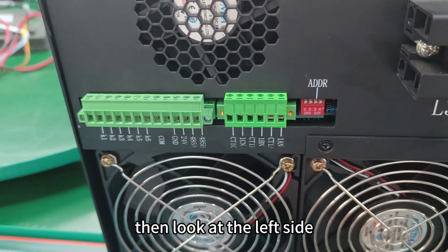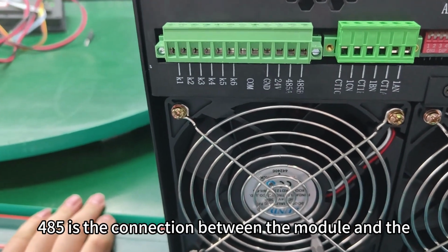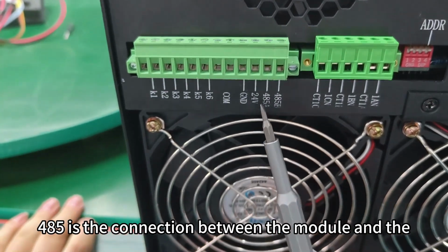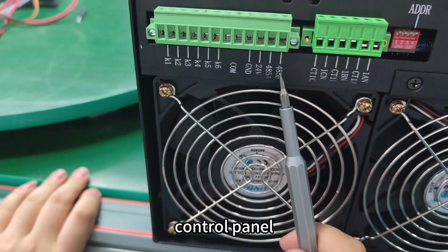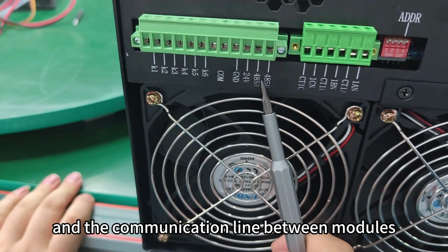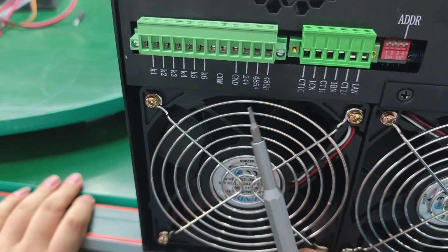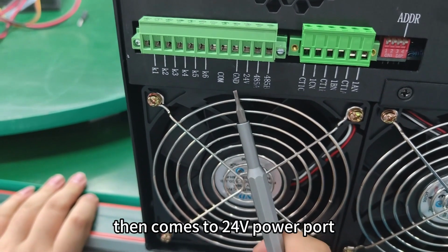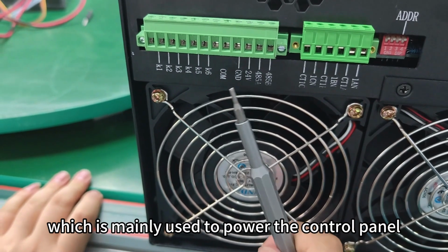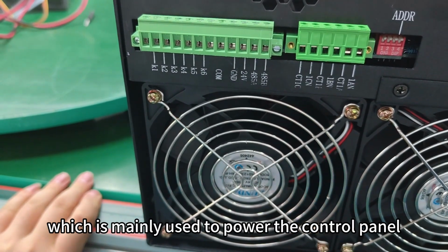Then look at the left side. 485 is the communication between the module and the control panel, and the communication line between modules. Then comes the 24 volts power port, which is mainly used to power the control panel.